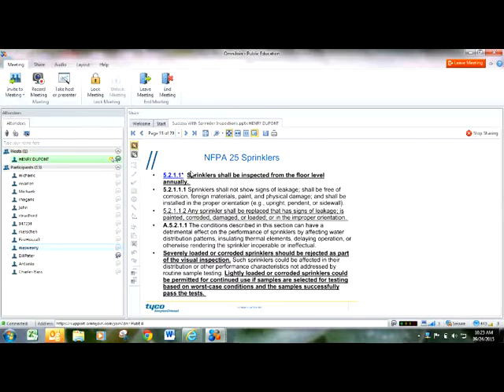Sprinkler head inspections. Sprinklers shall be inspected from the floor level annually. Any sprinkler head shall be replaced that has signs of leakage, is painted, corroded, damaged, or loaded, or in the improper orientation. Severely loaded or corroded sprinkler heads should be rejected as part of the visual inspection. However, lightly loaded or corroded sprinkler heads could be permitted for continued use if samples are selected for testing based on worst case conditions and the tests are successful.